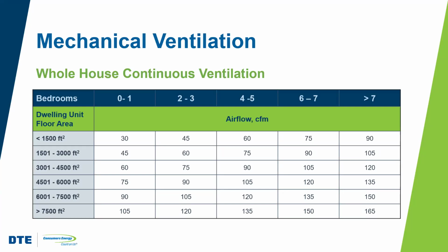We could do a combined system that does supply and exhaust. We call these balanced ventilation systems. They balance the air pressure in the house by bringing in and removing equal amounts of air. And then we have balanced ventilation with recovery, right, which can either be heat or energy recovery. So in addition to exhausting and bringing in air, these also extract sensible and latent energy from the exhaust airstream and use it to precondition the supply airstream, thus reducing how much the central system has to work in order to condition that air.